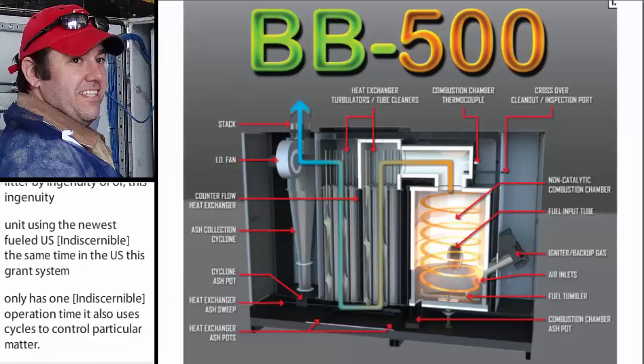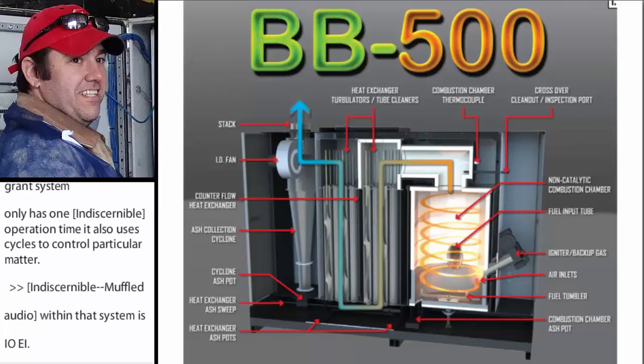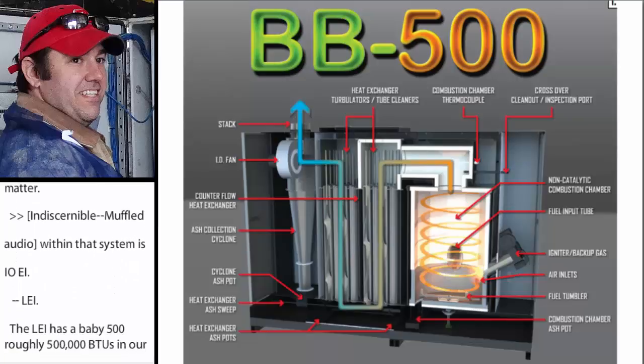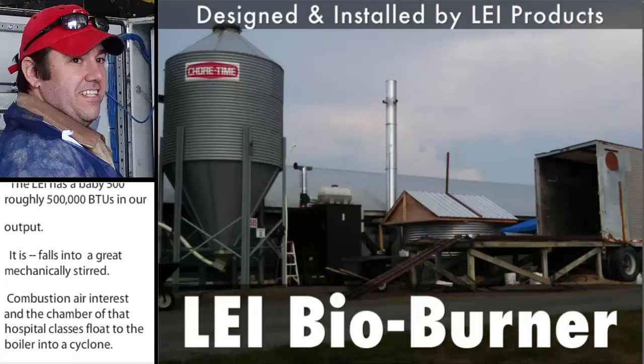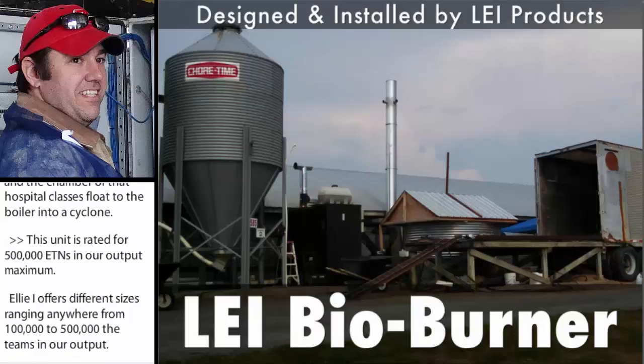The next system is by LEI. The LEI has a BB-500, roughly 500,000 BTUs an hour output. The fuel is augured into the combustion chamber where it falls into a grate and is mechanically stirred. Combustion air enters into the chamber and then the hot flue gases flow through the boiler and into a cyclone. LEI offers different sizes ranging anywhere from 100,000 to 500,000 BTUs an hour output. These units were initially designed for woody biomass and have been used on the farm with woody biomass for the past three years.